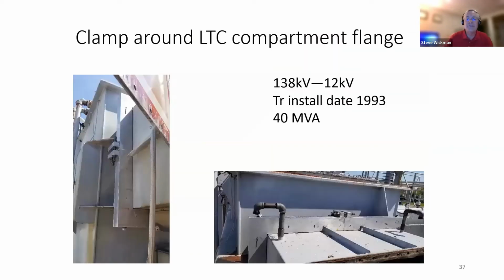I've got some pictures of some other, different repairs aside from the traditional piping flanges and bushings, such as some other flanges on transformers, to get your creative juices flowing on where else this can be used. You've got those big flanges that go around the perimeter of an LTC compartment. This is a 40 MVA 138 to 12 transformer.